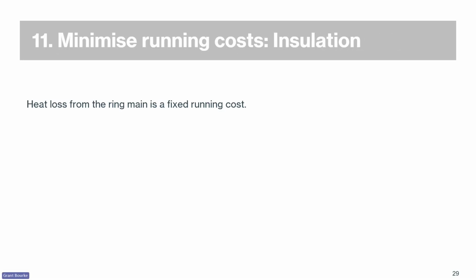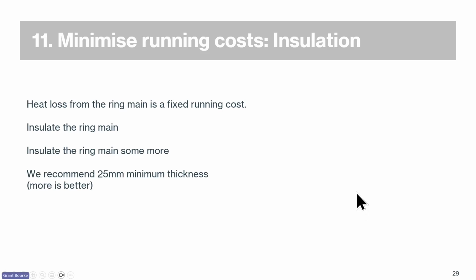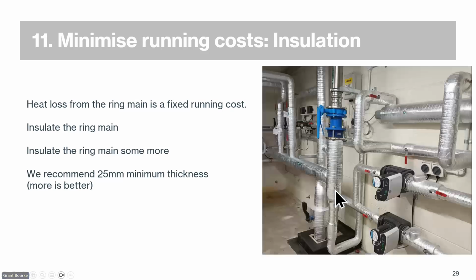So we want to minimize the running cost. As I said earlier, the heat loss from the ring main is a fixed cost. So the first thing we want to do to fix that is insulate the ring main. And then the second thing we want to do is insulate the ring main better. So we recommend 25mm thickness. More is better. This is what good looks like.